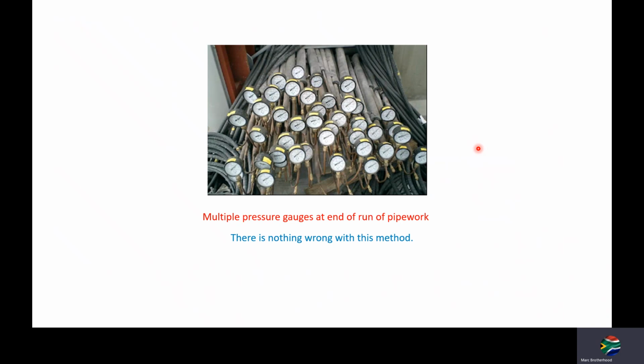So make a recording of that, and there's normally around a 1.4 psi drop per 1 degree drop in temperature. So if you have a 10 degree drop from the previous afternoon to the new morning, you're going to show just over 14 psi pressure drop, which is about 1 bar. And you're going to think you've got a leak on the system. You don't have a leak on the system. It's purely the ambient air that has dropped in energy.